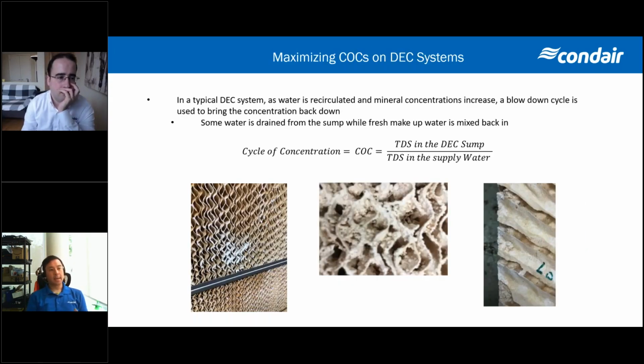So just to give you an idea here in terms of maximizing the water quality or water efficiency, what we do is effectively try and maximize the number of COCs, or cycles of concentration, inside of the DEC system. So the cycle of concentration is effectively the TDS in the sump divided by the TDS of the supply water. So how many times can we actually concentrate that water up before we need to drain that water out of the system? So typically in an evap system, we would have a blowdown cycle that would drain some of that concentrated water out while the inlet valve brings in fresh makeup water to maintain a specific TDS within that sump.